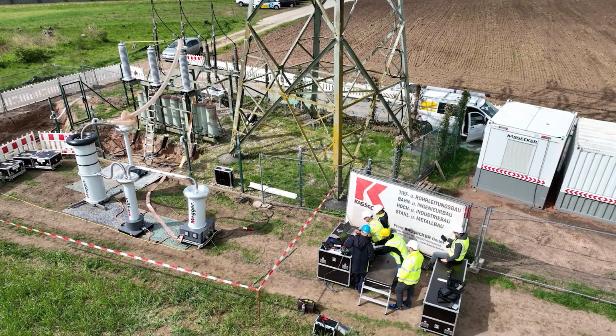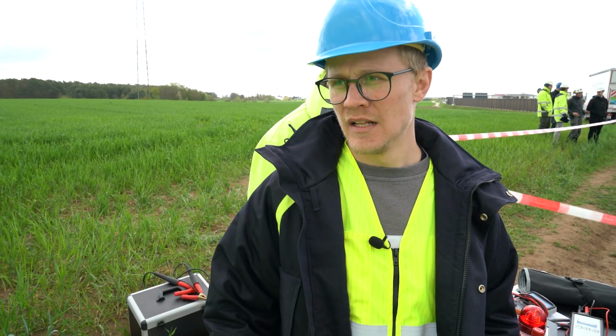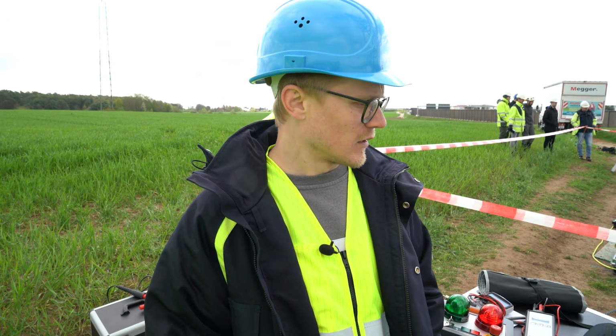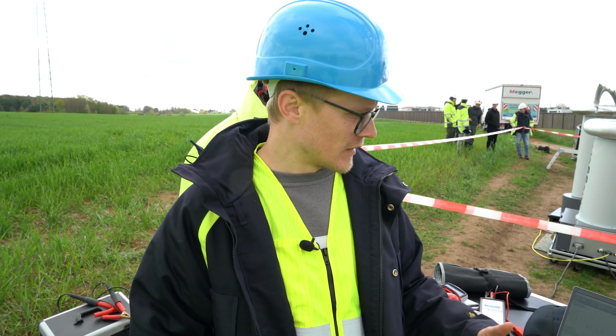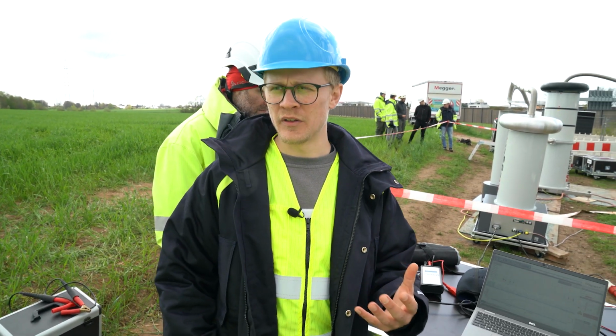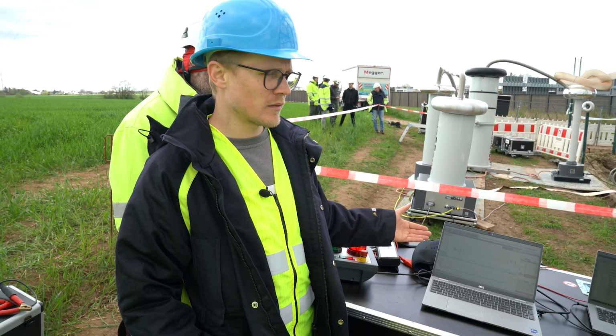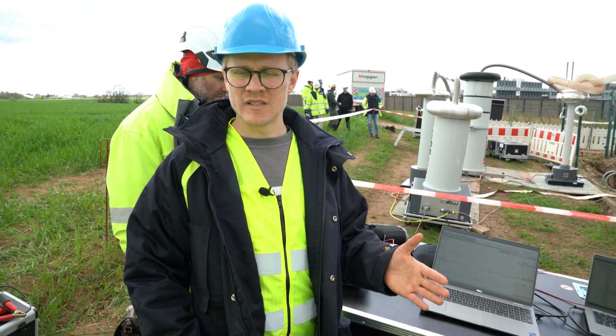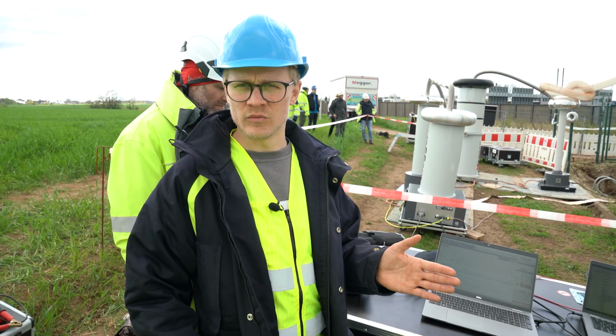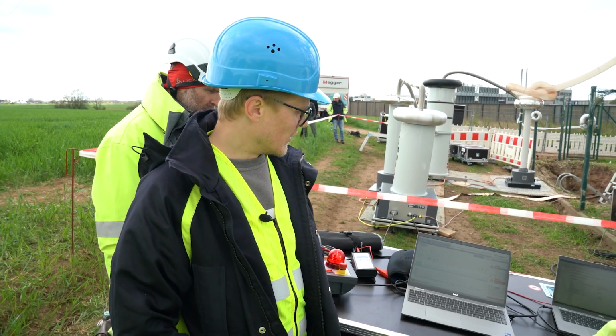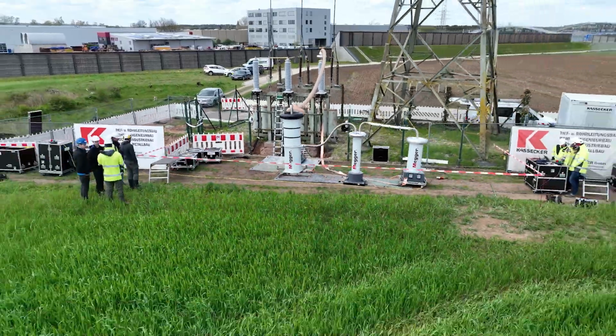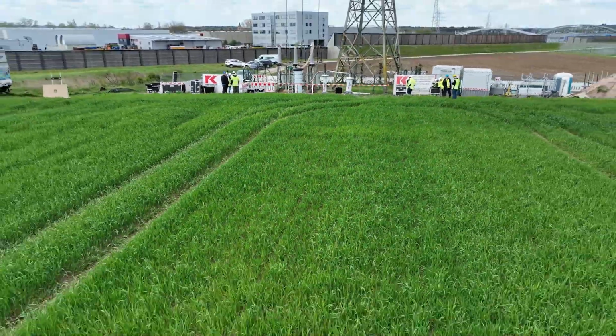Ultimately, the test fails if the cable breaks down during the test. Any other partial discharge measurement result requires a professional evaluation. We will evaluate this measurement data in our office and take another close look at the partial discharges. In the end, the customer receives our assessment of the condition of the cable and the end caps.